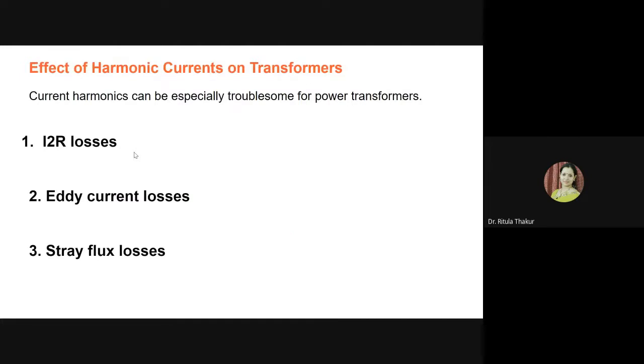Now if we talk about the transformers, mainly the current harmonics can be troublesome for power transformers. Mainly three types of losses are there. I square R losses, which I think many of you are aware of. For those who are not from an electrical background, I square R losses are due to the higher order currents within the transformer windings. So what is this I? I is nothing but the current.